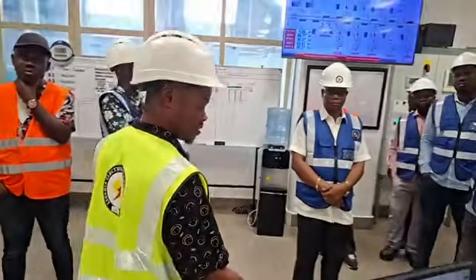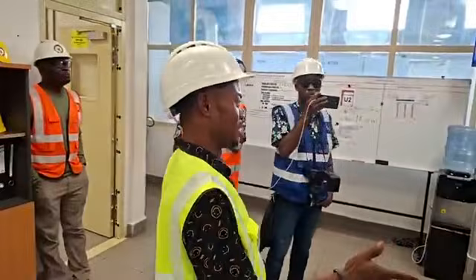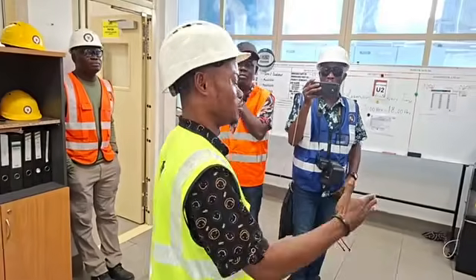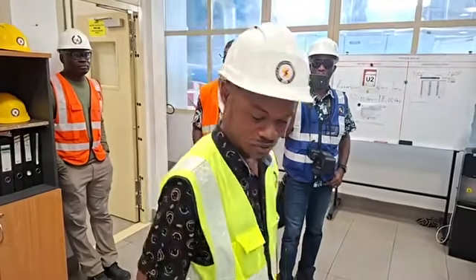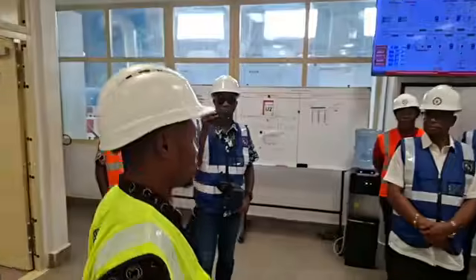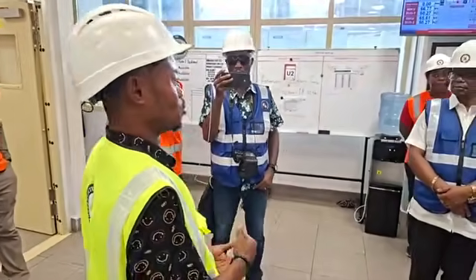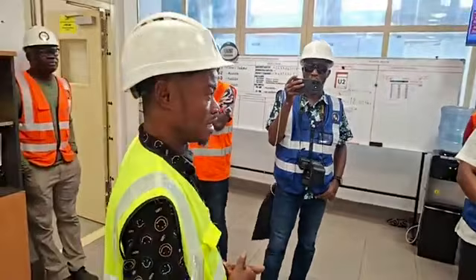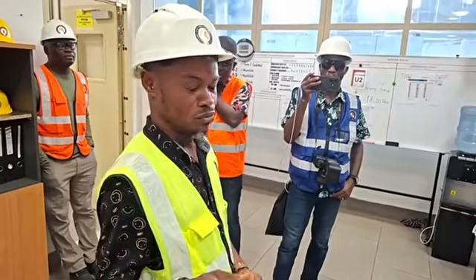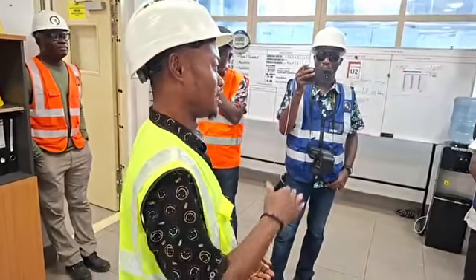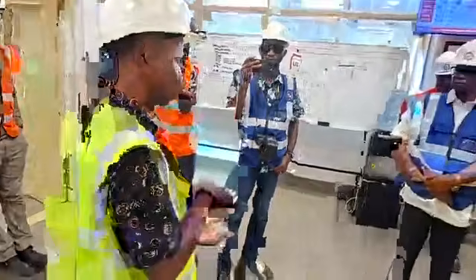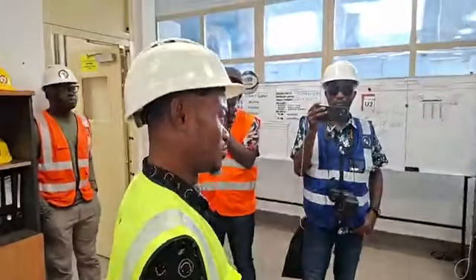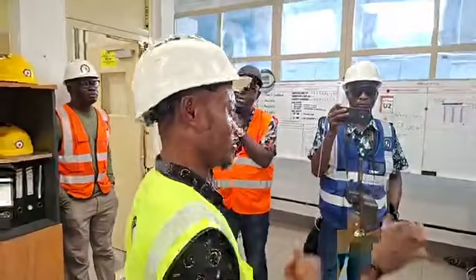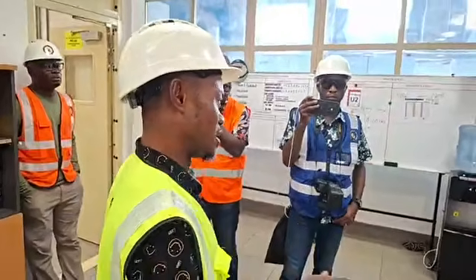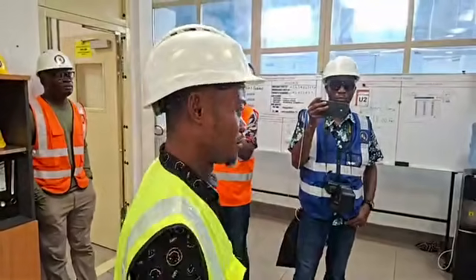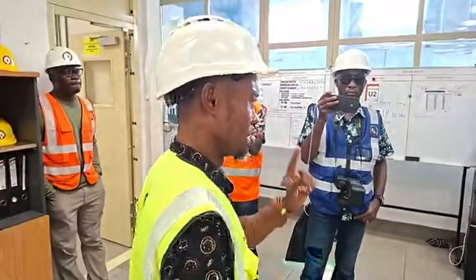So currently, in our dry season operation, we are more like a peaking plant where we come on by the evening hours to support the grid. Currently, our reservoir level is 28.42. So we'll come on by 6 p.m. and run 2 units up to 2 a.m. By 2 a.m., our reservoir level will be low, so we'll shut both units down, then we conserve water for 4 hours. By 6 a.m., we'll come on and support the grid with 1 unit.